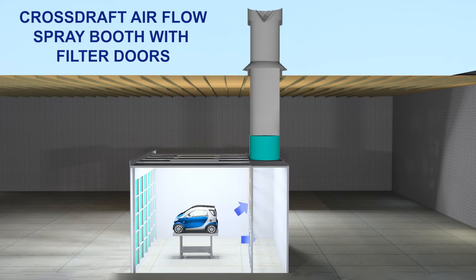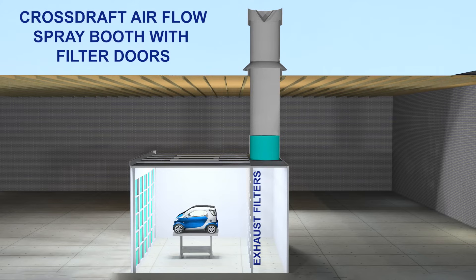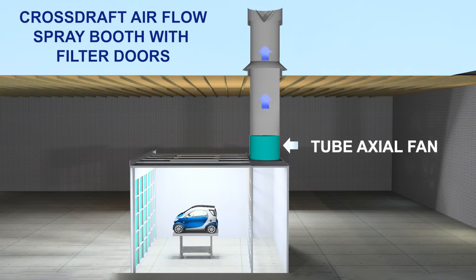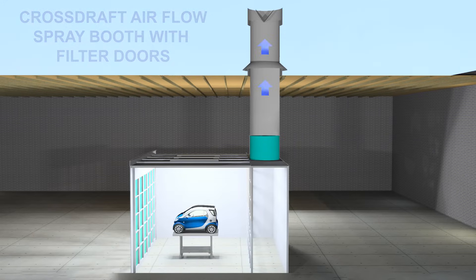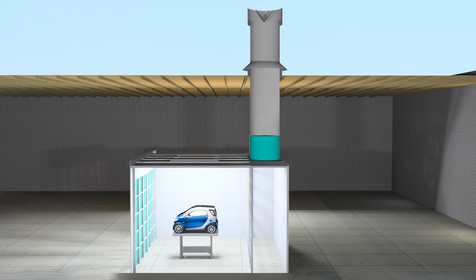The Crossdraft spray booth draws outside air into the booth and exhausts the paint-laden air through exhaust filtration at the rear of the booth. From there, it passes through the exhaust fan and up through the roof of your building in specialized ducting to the outside. The exhaust fan is a non-sparking tube axial fan, so the flammable paint fumes and overspray not collected by the exhaust filtration will not catch on fire. This design is the most common type of airflow used in all industries.